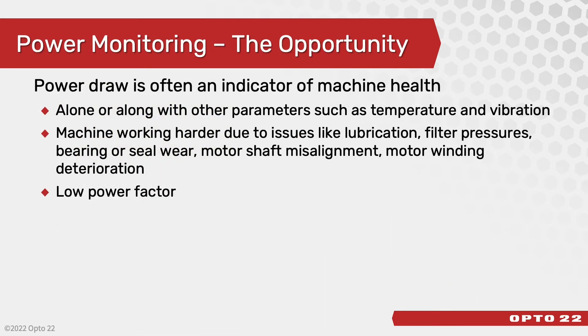Let's move on to power monitoring. What is the opportunity there? As I mentioned before, power draw is often an indicator of machine health. Excessive power draw can be an indication of problems like lubrication, filter pressures, bearing or seal wear, motor shaft misalignment, or motor winding deterioration.